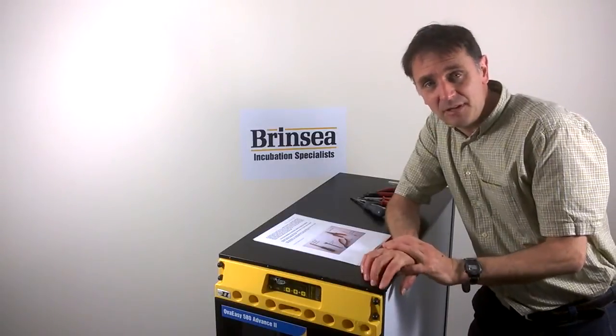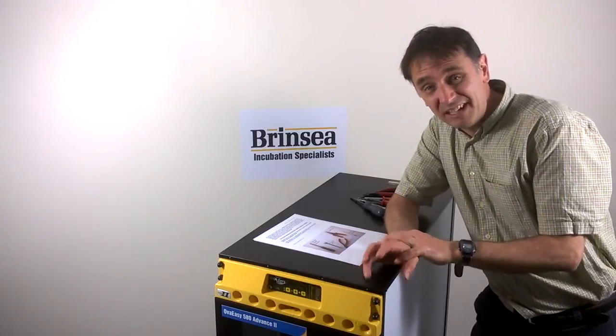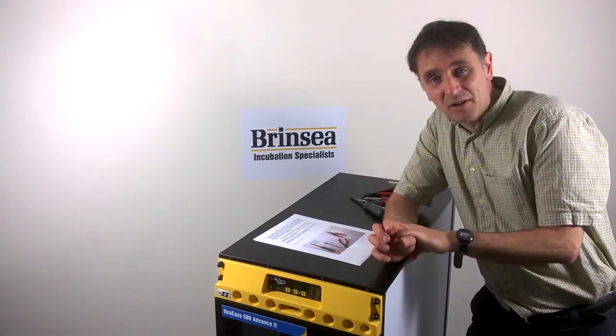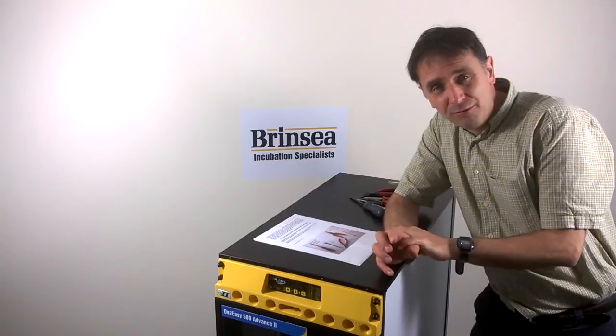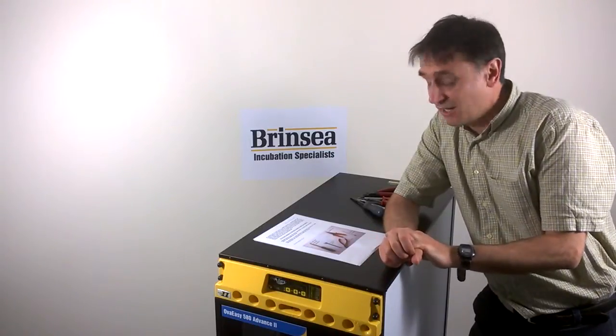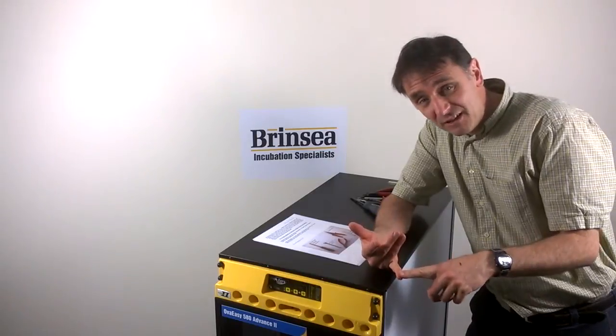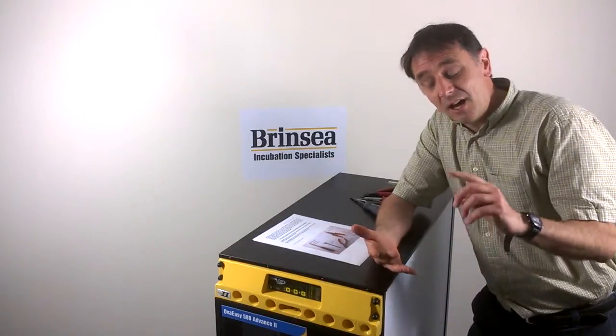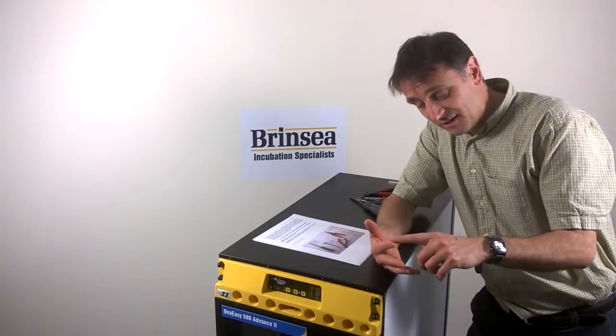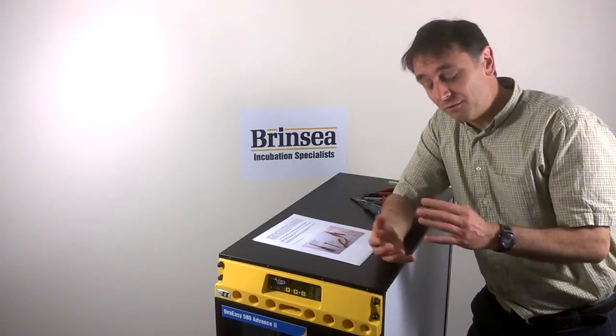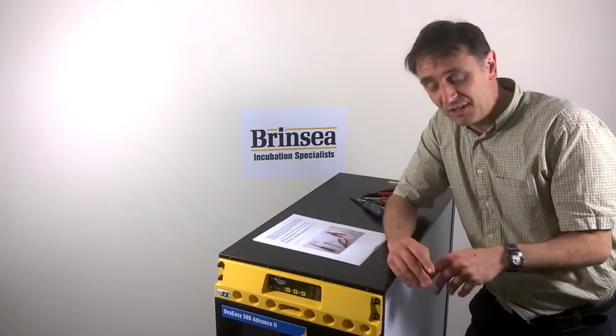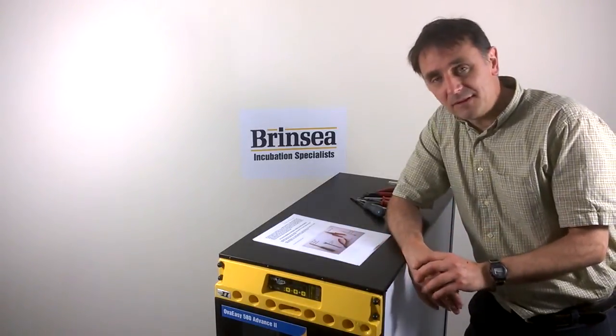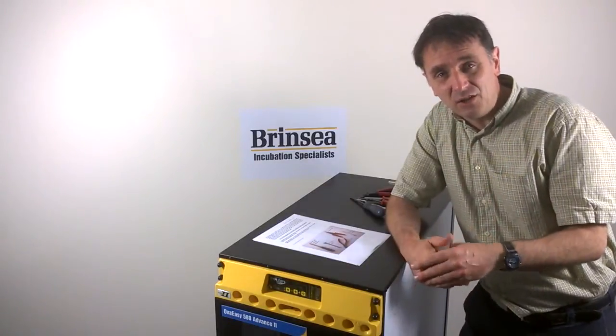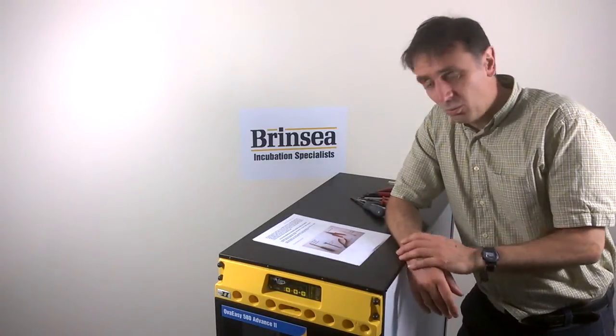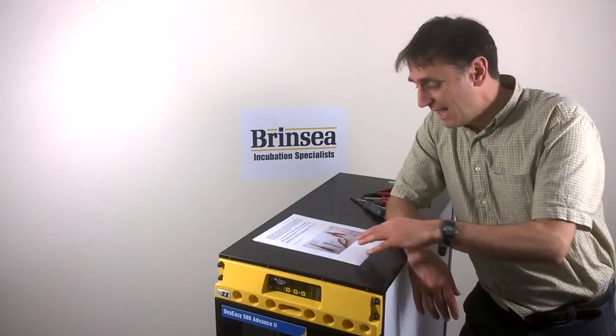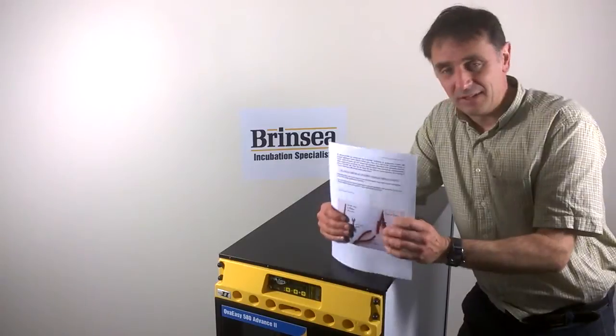So this little clip is to demonstrate how it's really relatively easy to replace the control module on an OVAEASY Series II machine. Now that includes an OVAEASY 580, an OVAEASY 380, an OVAEASY 190 and an OVAEASY Hatcher. It does not include the OVAEASY 100, which is slightly different and needs to be looked at separately. So, in order to replace the control module on one of these machines, we really need to start with a set of instructions like these.